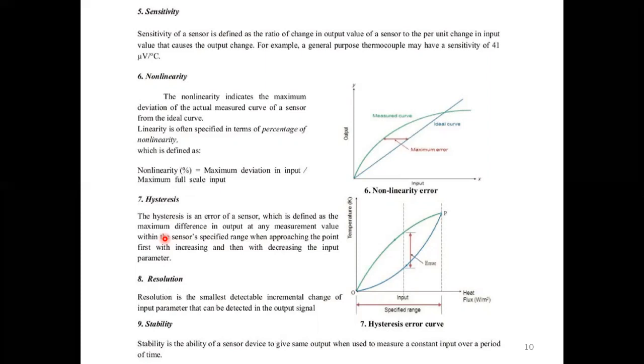That is sensitivity. Okay. Next one, non-linearity. The non-linearity indicates the maximum deviation of the actual measured curve of a sensor from the ideal curve. In this curve, this is the ideal curve, this is the measured curve, and this is the non-linearity of the sensor. We can also call it an error. Linearity is specified in terms of percentage of non-linearity. Non-linearity percentage is equal to the maximum deviation divided by the maximum full scale input. This is the maximum deviation, divided by the maximum full scale input, that is non-linearity.